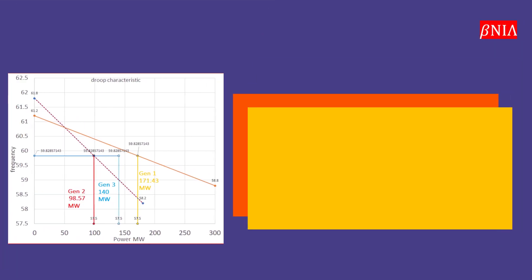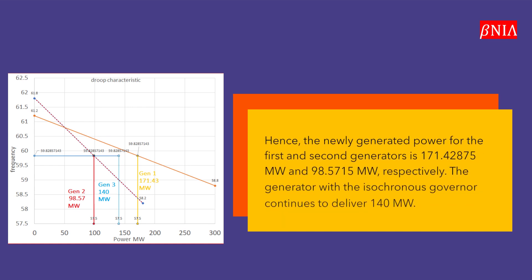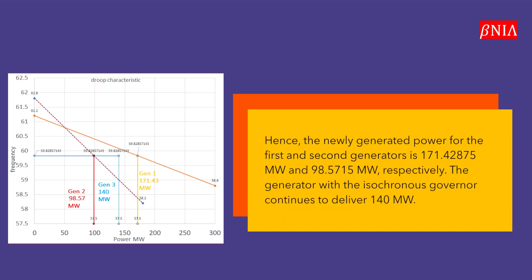Hence, the newly generated power for the first and second generators is 171.42875 MW and 98.5715 MW, respectively. The generator with the isochronous governor continues to deliver 140 MW.